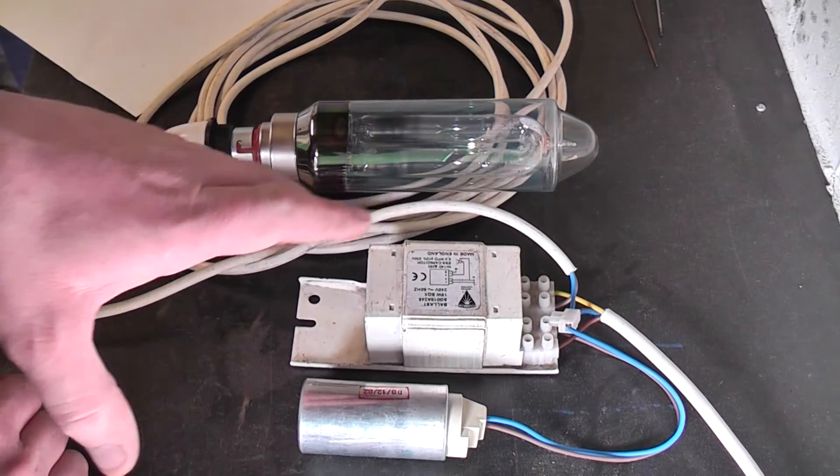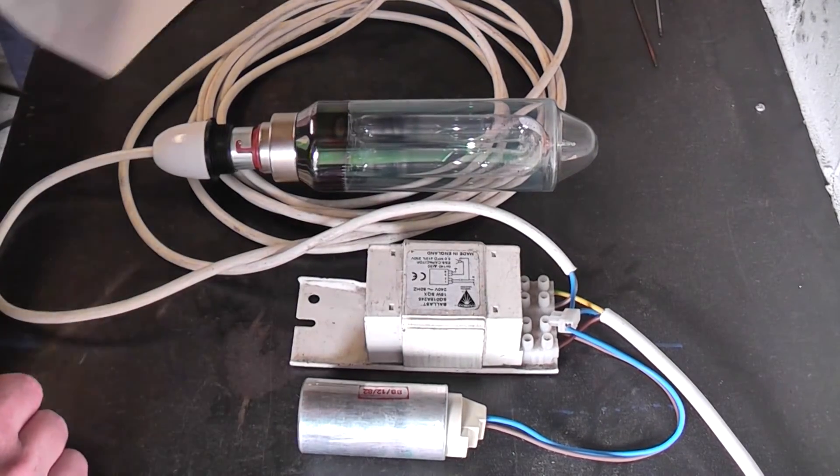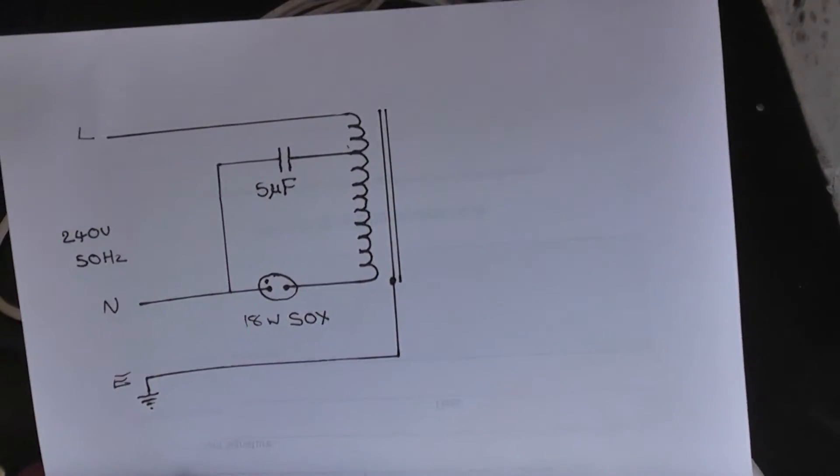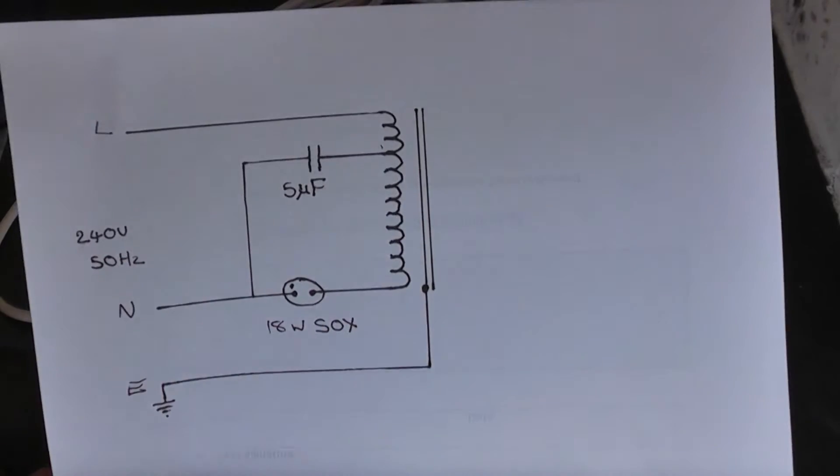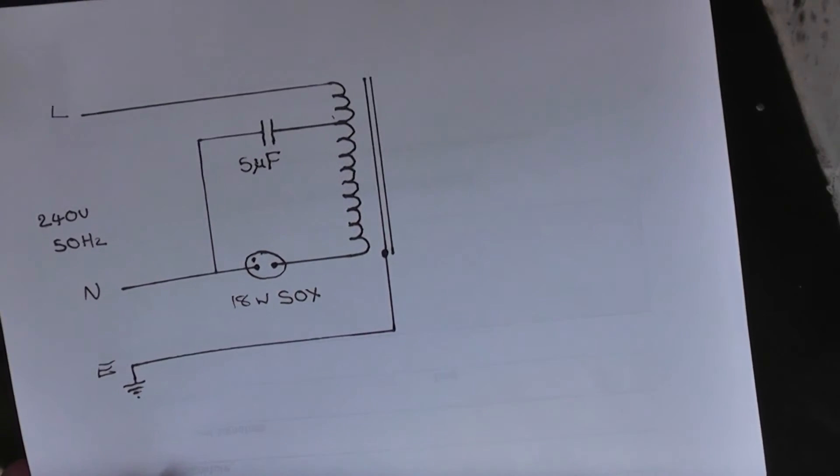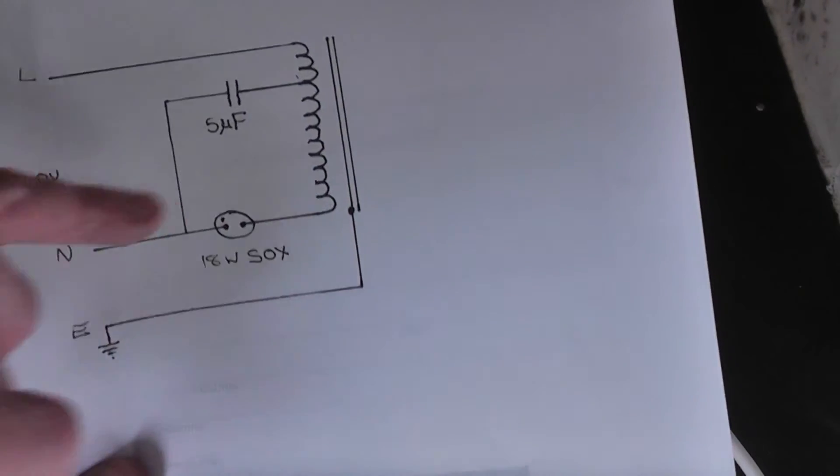Now the interesting how they're actually driving this circuit is what we've got is you've got your ballast there. You've got a 5 microfarad capacitor which serves as two purposes, it serves as power factor correction when the lamps running but it also helps to start the lamp.